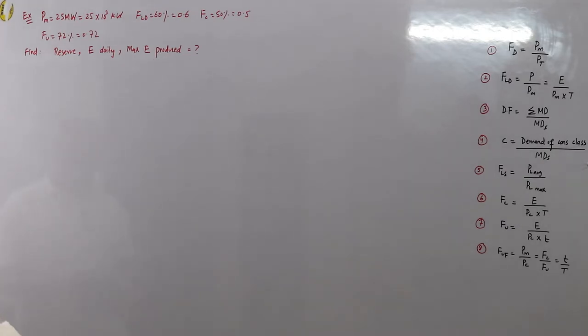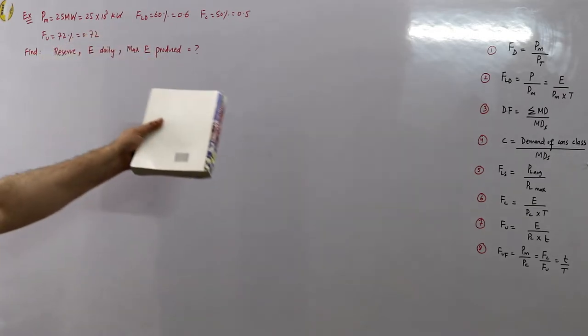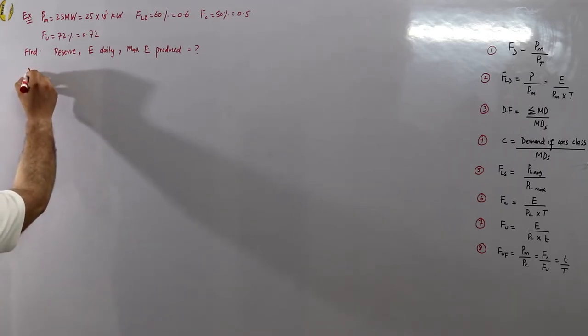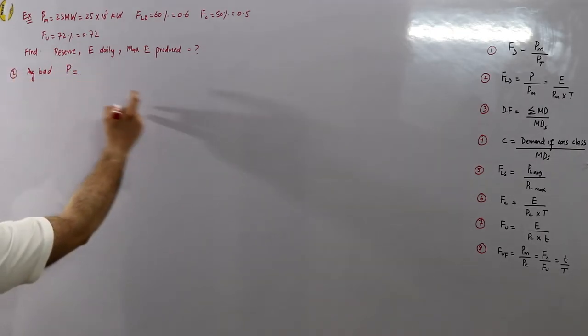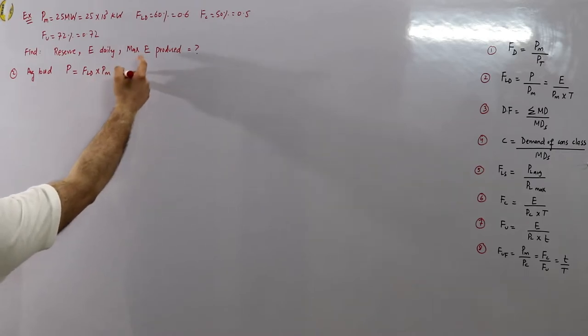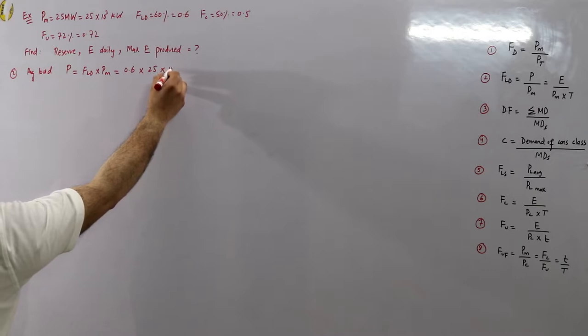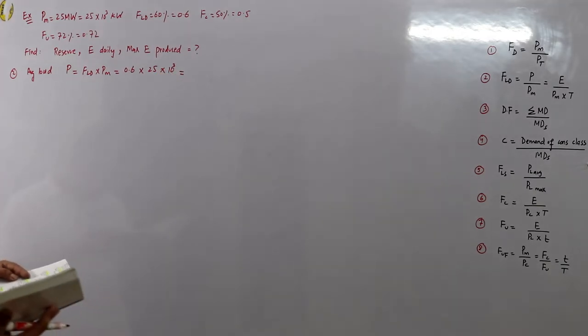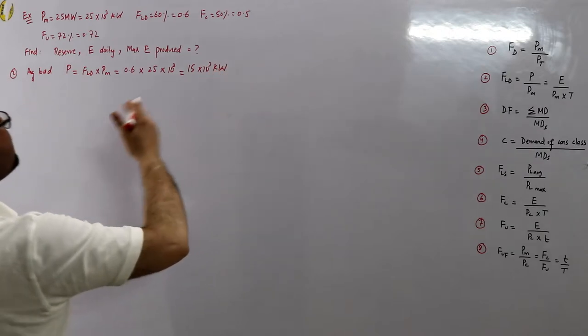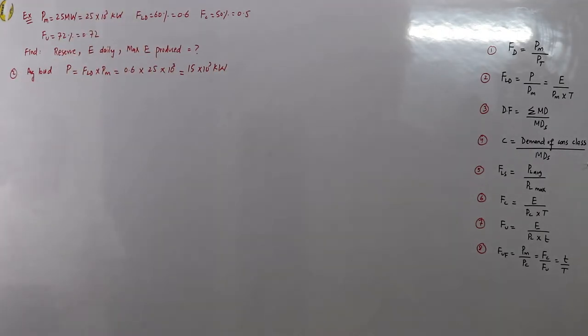First, from the definition of load factor — average load divided by maximum demand — we can find the average load. Average load P equals FLD multiplied by PM, which is 0.6 × 25×10³ kW, giving us 15 megawatts.